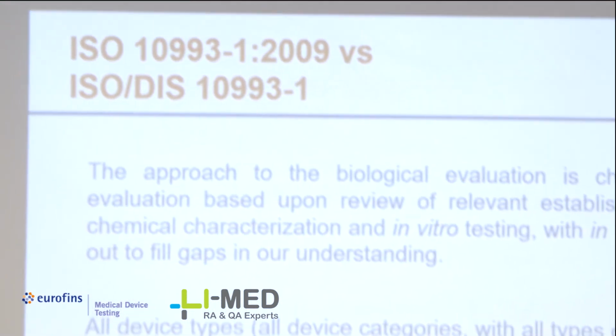So the approach is changing a lot. We are moving from a checklist approach in which we need to perform all the tests to a much more structured program of biological evaluation in which, first of all, we need to collect all useful data regarding physical and chemical information. And then, evaluating this data from a toxicological point of view, we can decide if further tests are necessary or not. And just for your information, ISO 10993-18 that deals with the chemical characterization and ISO 10993-17 that deals with the toxicological evaluation are now under review.